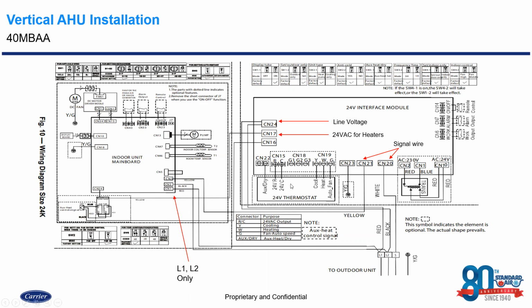Okay, the biggest thing to note on here is if you look where we have this 24-volt thermostat. So we talked about a 5-wire thermostat. So of course we have our R, which is our hot, our C, which is our common. We have our Y1 for our cooling call, W1 for our heating call, G for our fan. Okay, but now you see this separate connection over here, which is auxiliary and dry. Okay, this is where we're going to wire up that W2 terminal to, or if you want to set up the auxiliary dry contact on that thermostat if it has one, you can wire that to CN22 and you can connect to either terminal. It does not matter what terminal you connect it on, like depicted in here. If you look, if you hook it up to the left terminal, it's doing the same thing. But this is the signal for where the interface interprets a call for W2 as the time to turn on those electric heaters, depending on whatever threshold that you set. So the biggest thing to note there is that your W2 is going to wire to CN22 to be able to send that control signal to bring on that electric heat.